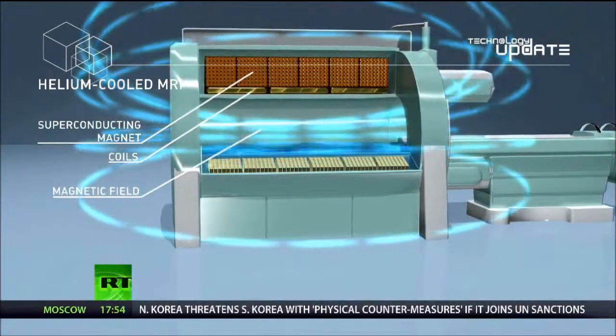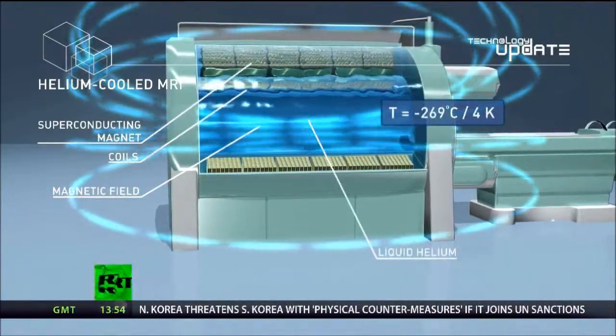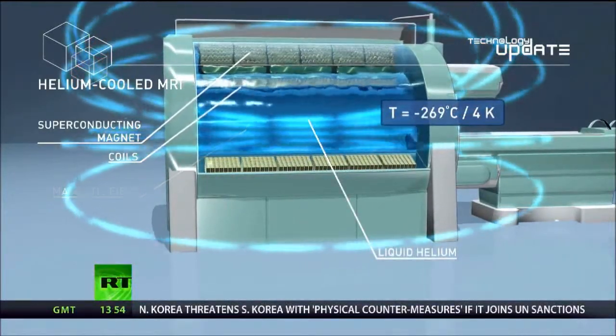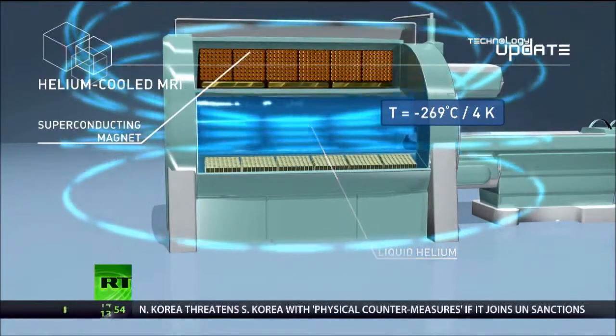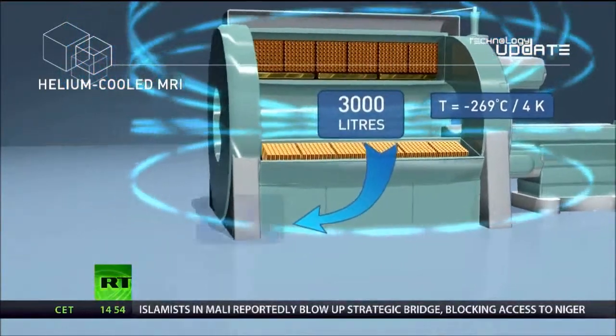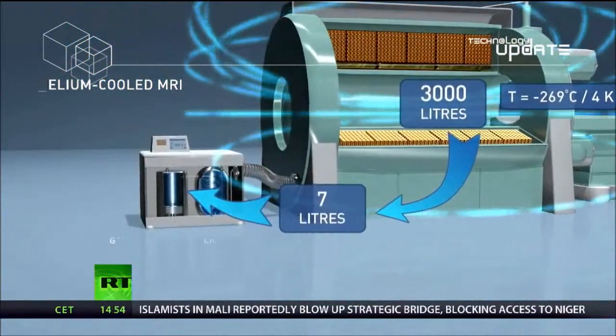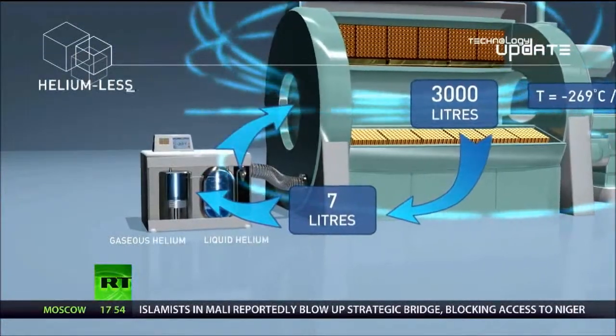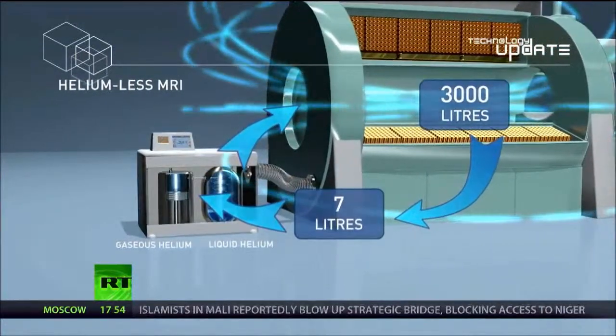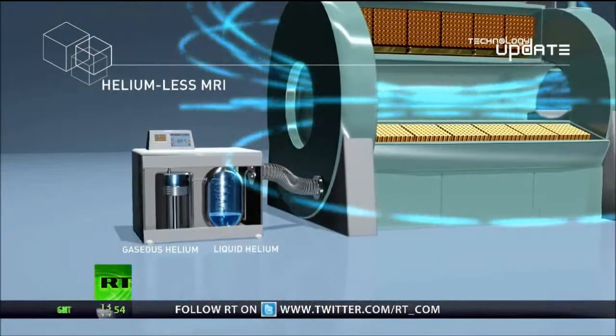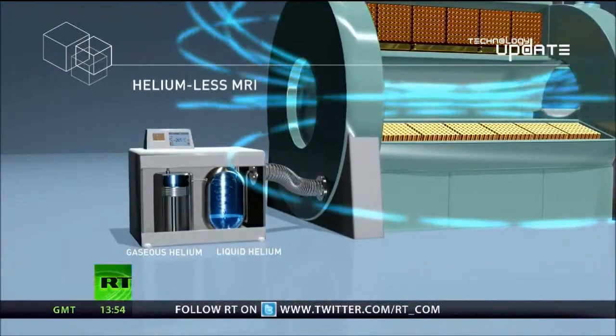Central to all this is the primary magnet's superconductivity, which eliminates resistance and is only attained by cooling it down with liquid helium. At the Lebedev Institute, they've developed a liquid helium-free MRI scanner. Now, it doesn't actually get rid of the stuff altogether, it just outsources the job to a separate apparatus that cools the coils using much less liquid gas.